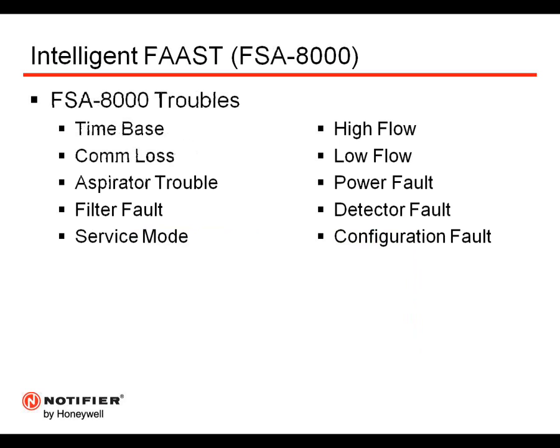So there are a number of troubles that could potentially be enunciated from an FSA 8000: time base trouble, communication loss trouble, and if there was a trouble with the aspirator or filter, that is going to create a trouble. It can be put into service mode, which I'm going to talk about coming up in a couple of slides. High flow or low flow, which could have to do with potential troubles with the pipe network, as well as a power fault, detector fault, and a configuration fault.